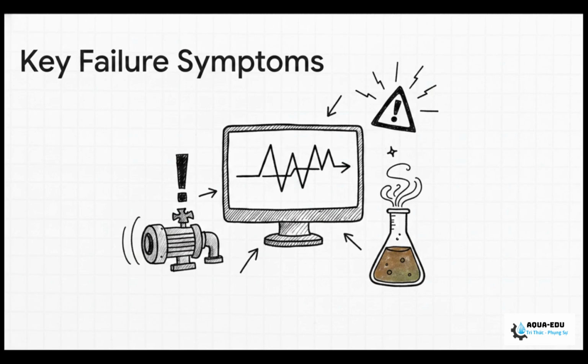Now, I really need you to watch out for these exact symptoms on your shift. Picture this. You're looking at the SCADA values and they're jumping wildly. I mean, going from 6.0 up to 9.0 and then crashing back to 5.5 in just a few minutes, even though the inlet water hasn't changed at all. Or maybe your dosing pumps are running nonstop, or they've just completely frozen up. You might even see the transmitter itself flashing a bright red out-of-range fault. Or, sometimes you just notice the inlet water suddenly smells or looks totally off, but that pH value on the screen hasn't moved a single inch. Guys, these are your major red flags.